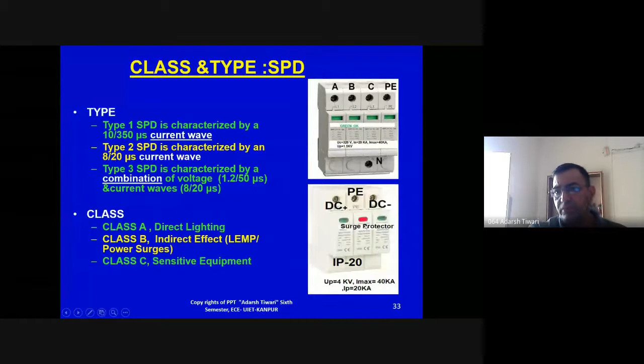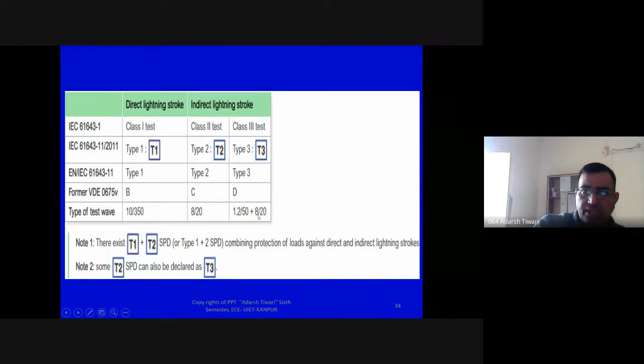So there are different standards and different combinations that we can use for the direct stroke and for the indirect stroke, like this IEC 61643-11-2011. For direct stroke, T1. For indirect stroke, we can take type 2, type 3. So these are the waveforms, like 10 by 350, 8 by 20, and this is the combination, where the first is for voltage and second is for the current. So type 1, type 2, type 3 we have already discussed.